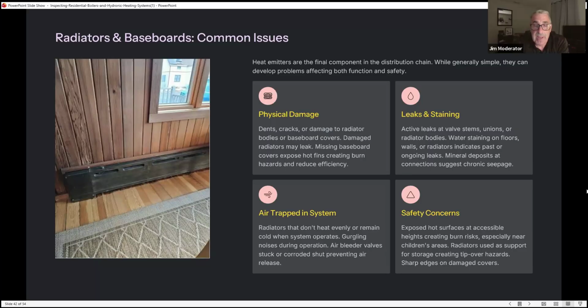Mineral deposits. Air trapped in systems: radiators that don't heat evenly or remain cold when the system operates, gurgling noises during operation, an air bleeder valve stuck or corroded, preventing air release. So these are safety concerns. Hot exposed surfaces at accessible heights create a burn risk, especially near children's areas. Radiators used as support for storage create tip-over hazards, sharp edges, and the like. I always say if you've got radiators and kids, you want to put covers on them, especially if they're young.